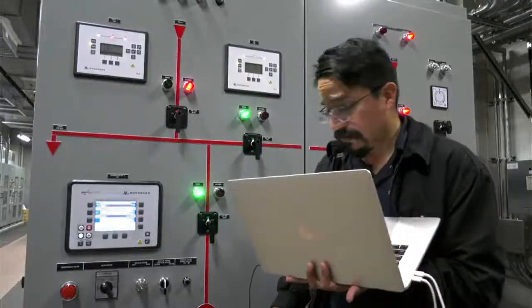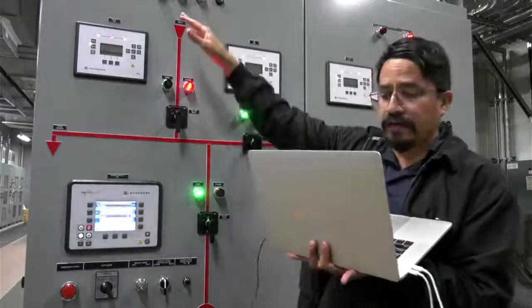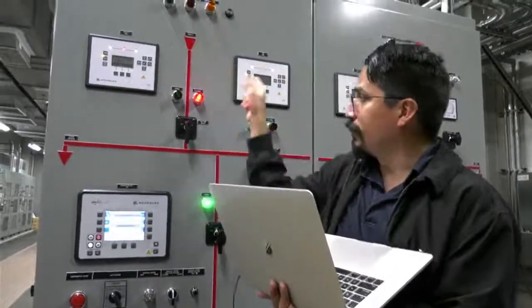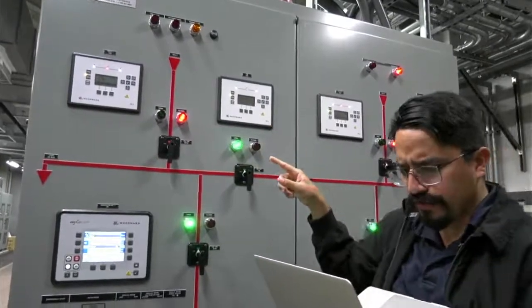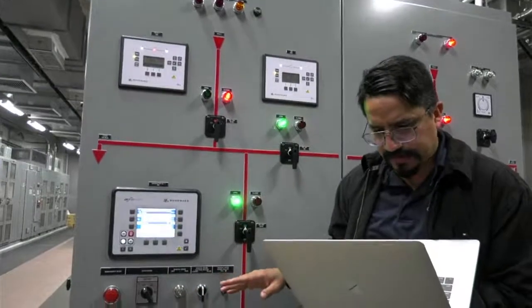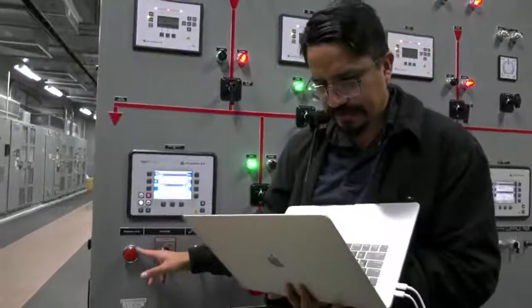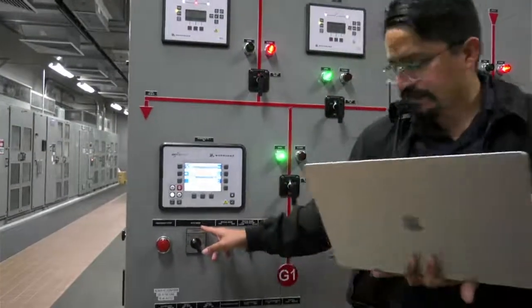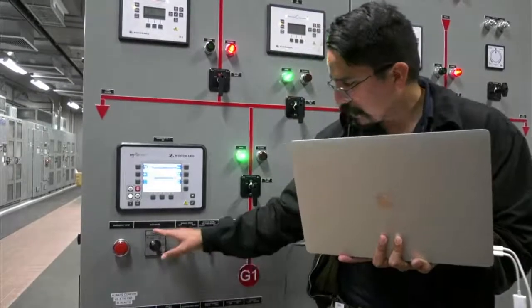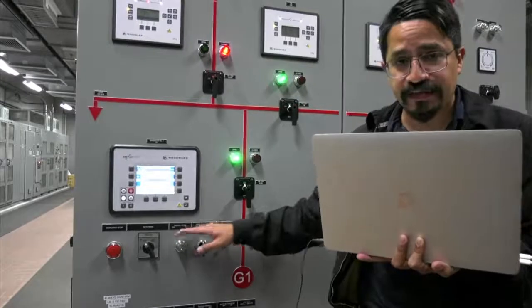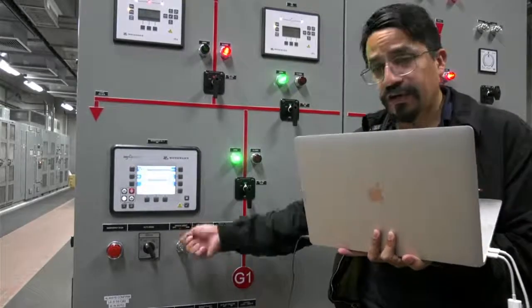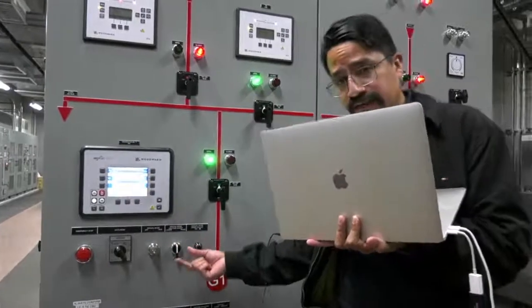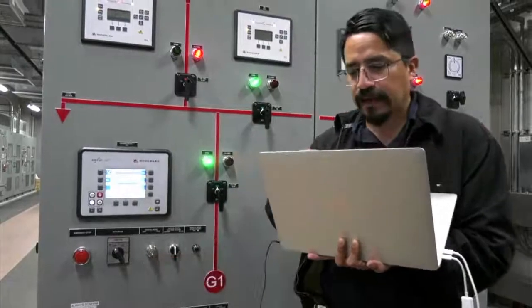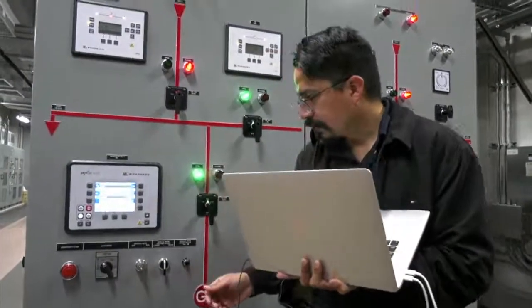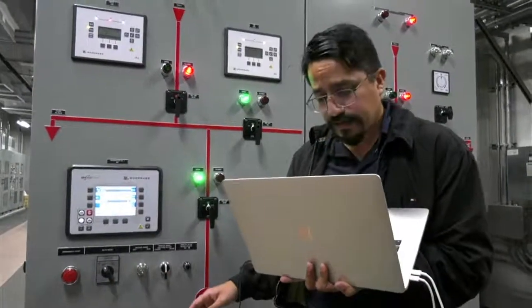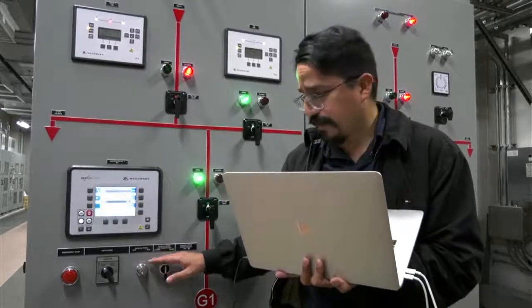So we were talking about the groups, right? Groups number 1, 2, 3, and we are going to continue with group number 5, which is over here. We talked about the emergency e-stop. We talked about the auto mode, which is only available when the system is in auto. We talked about the 3 switches for manual control, to run the engine, to control the voltage, and to move the speed, which is the frequency. I'm on sheet number 31, by the way, so you can see more details about the switches over there. But these are the main switches for manual control.